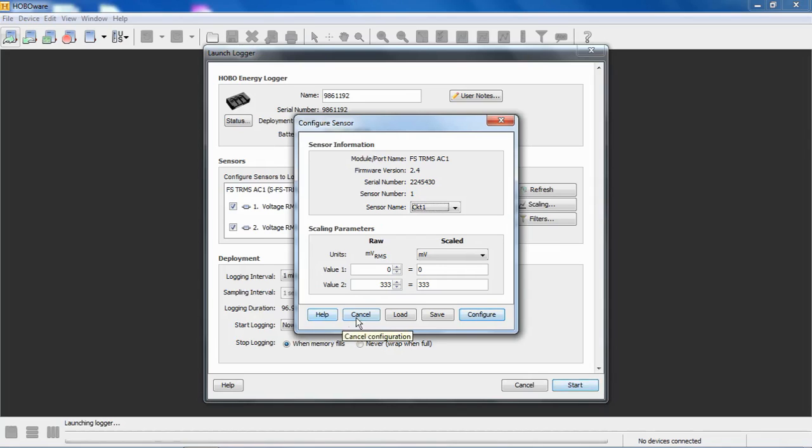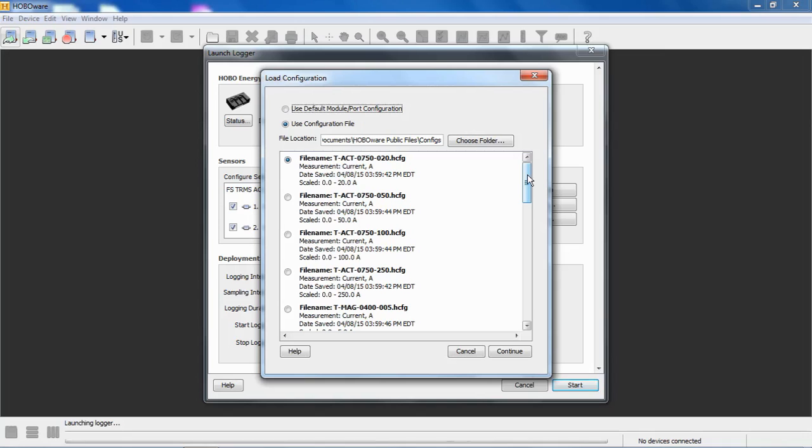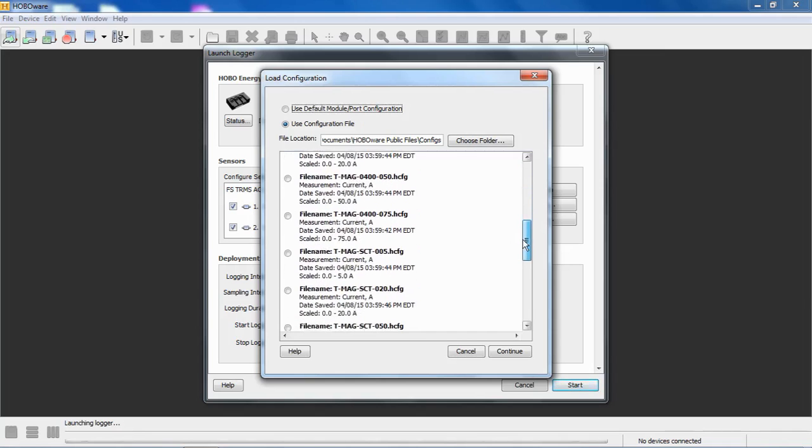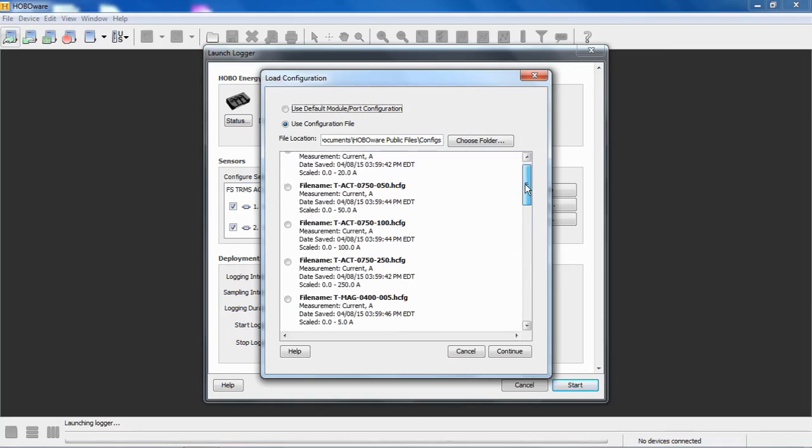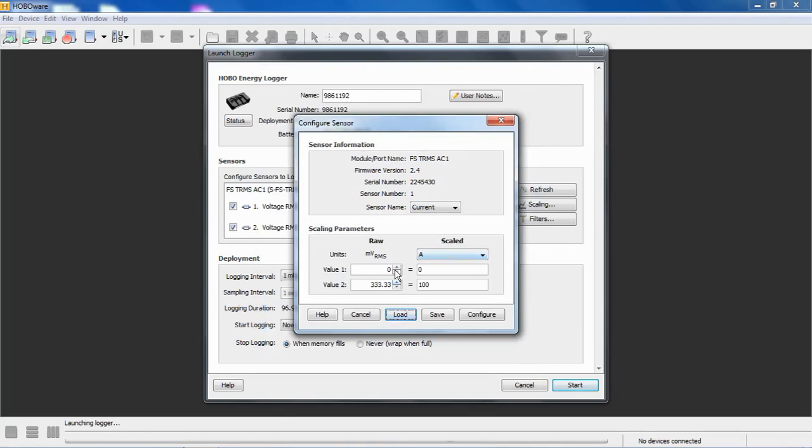If we click on load, there's a folder in your HoboWare public files folder under my documents that include pre-configured files for different types of sensors that we currently sell that are compatible with this device. You can see here, this is a 20-amp CT, a 50-amp CT, a 100-amp CT. These are the ACT sensors. We also have pre-configured for the Magnelab versions, the 5-amp, 10-amp, 20-amp. So if you're using one of these sensors that you purchased from us, you can simply select that. If you just click on that little radio button and click continue, notice now that our scaling is configured correctly.